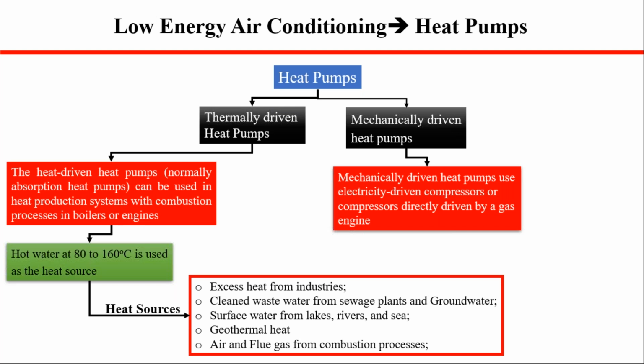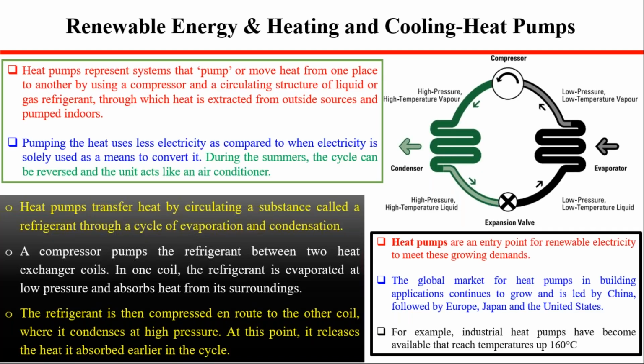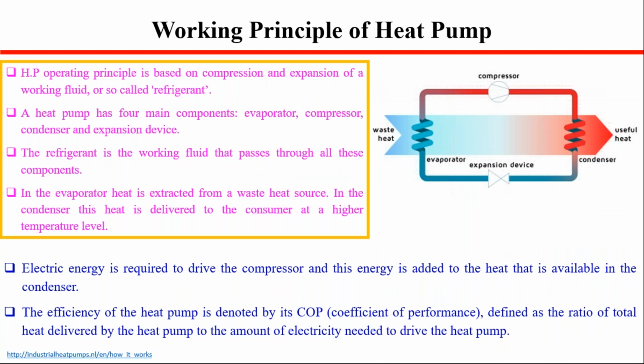They use hot water or heat in the range of 80 to 160 degrees centigrade, from the solar heat, from the waste heat available, geothermal heat, or the air and the flue gas from the combustion process. This is a general overview that I have included in this slide, and this is the cycle. You can go through this, and this is very common, how the heat pumps work. I will not go through this because I'm running out of time.